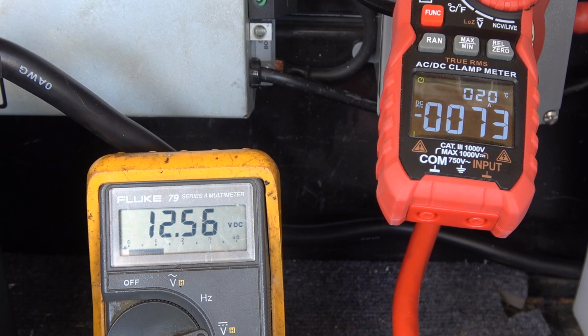0.73 amps, 12.5 volts on the battery terminals. The fan you hear is my inverter. So 1,000 watts. There we go, 96 amps, 12.3 on the terminals. So it seems to be handling its max discharge rate. Let's go above it now and see what happens.